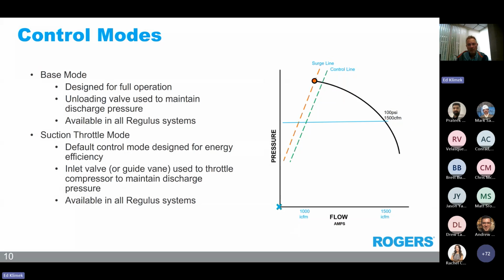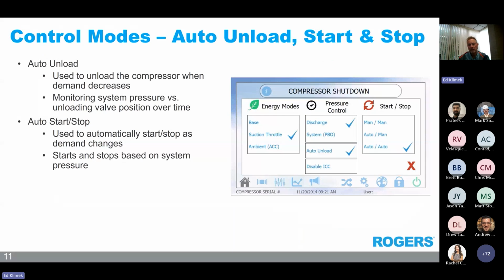So this slide here is going to animate suction throttle control. The X that you'll see, which is right here, is the compressor operating point. So as demand decreases, the compressor will turn down, providing energy savings and eliminating wasted energy through blow-off. Another feature is auto unload, start and stop. These modes are great for users who have changes in demand and the desire to unload or stop compressors that are no longer needed to meet demand.